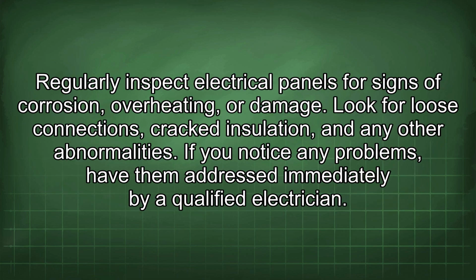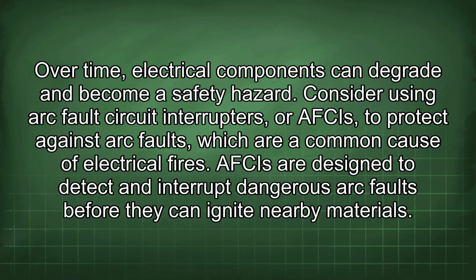Regularly inspect electrical panels for signs of corrosion, overheating, or damage. Look for loose connections, cracked insulation, and any other abnormalities. If you notice any problems, have them addressed immediately by a qualified electrician. Over time, electrical components can degrade and become a safety hazard.